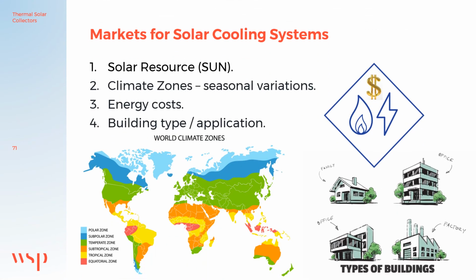The seasonal variations within a climate zone have a strong influence on the performance of a solar cooling system. A solar cooling system will provide the best economic performance if the solar array can be utilized as much as possible. So from the point of view of economic feasibility, it is imperative to have either high annual cooling loads or combined annual heating and cooling loads. Energy cost is also a very important factor when economic feasibility is calculated. The local cost of energy, electricity, natural gas and water determine the operation cost of the heating and cooling system. This applies to both standard and solar-driven systems. Therefore, the higher the cost of utilities at a given location, the higher the savings that can be made by a solar cooling system.